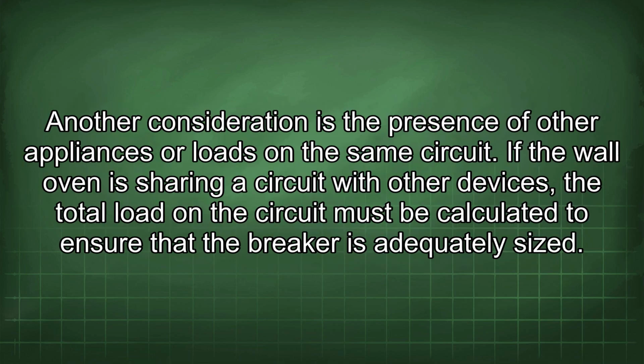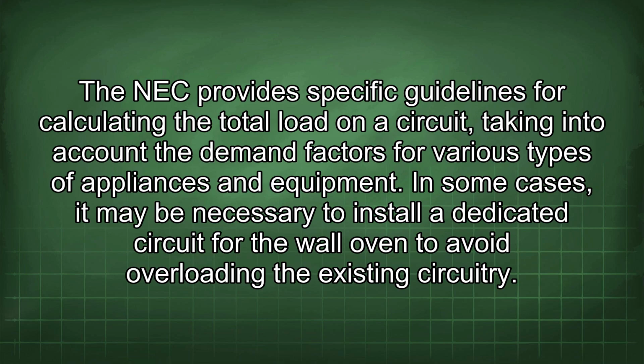Another consideration is the presence of other appliances or loads on the same circuit. If the wall oven is sharing a circuit with other devices, the total load on the circuit must be calculated to ensure that the breaker is adequately sized. The NEC provides specific guidelines for calculating the total load on a circuit, taking into account the demand factors for various types of appliances and equipment.